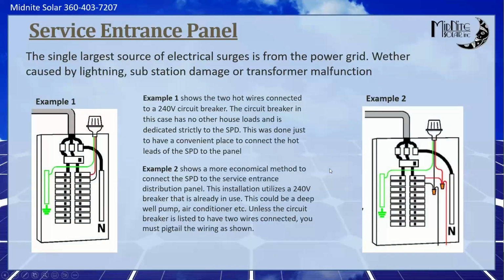So the first one, which is, like I said, a no-brainer, is your service entrance panel coming in from the utility, if you have a utility. As close to the main breaker as possible. You'll notice in both images we're tapped into the top right near the main breaker. You can do a dedicated breaker if you have the space, a 20 or 30 amp AC 2-pole breaker. Or if you don't, you could grab a circuit near the top, like a well pump or something like that, and you can splice the wires using the appropriate splices, whether it be wire nuts, Wago connectors, Polaris connectors, whatever you feel comfortable with, as long as it's listed for that job, you're good to go.